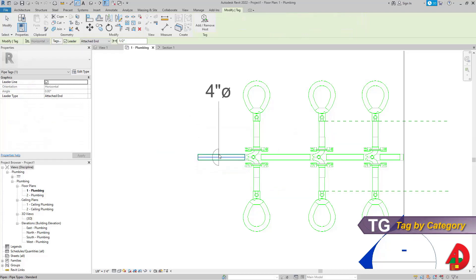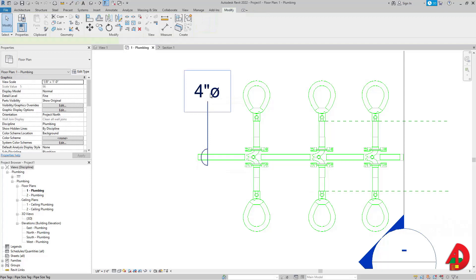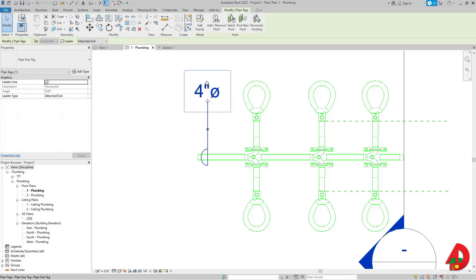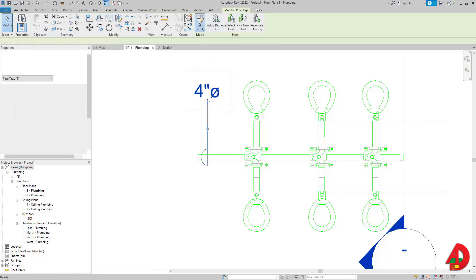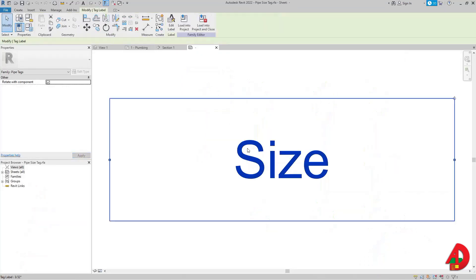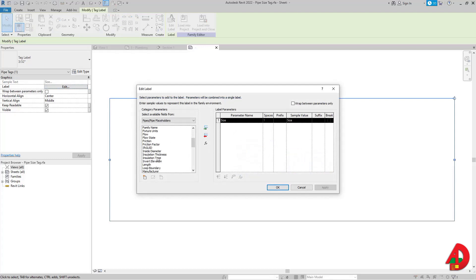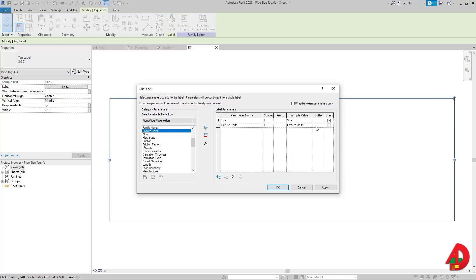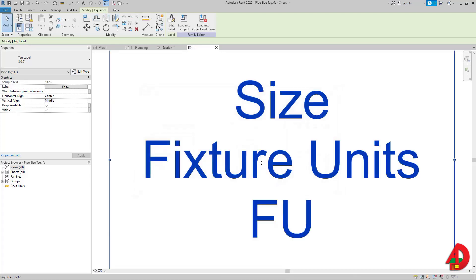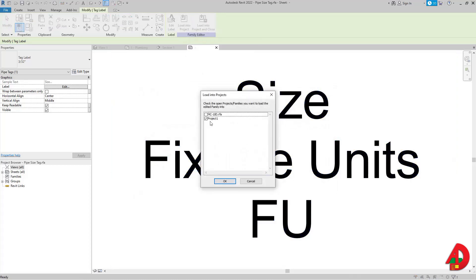Now let's use a pipe tag to show the fixture units. I'll place a pipe tag, but by default it shows the diameter. To show fixture units, I need to Edit Family on the pipe tag, click on the label, and edit it. Right now I just have 'Size.' I'll find 'Fixture Units,' bring it to the right side, check 'Break' so they appear on separate lines, and add a suffix 'FU' in capital letters. Then I'll press OK and load this back into the project, overriding the existing version.